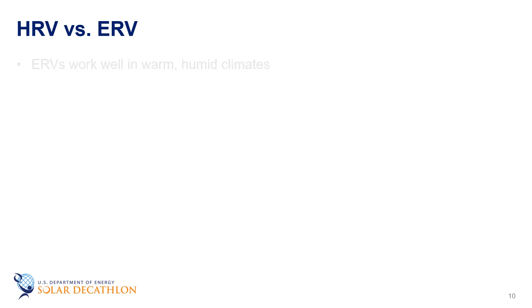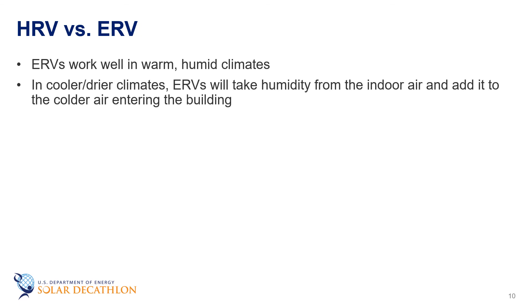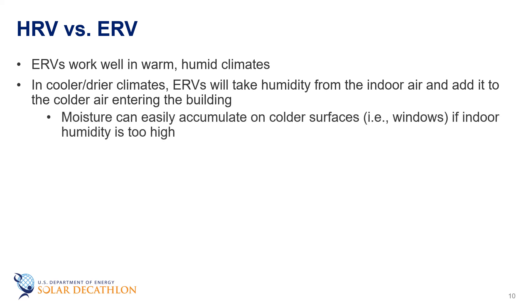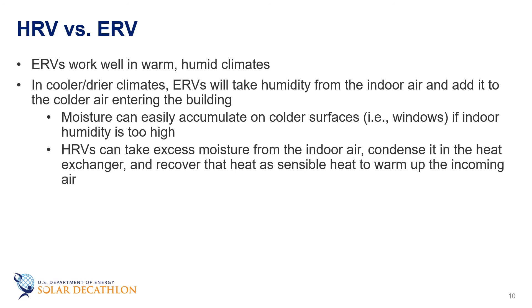As a caution, however, this works well in humid climates. As the climate becomes cooler and the heating loads dominate, the energy recovery ventilator will take the humidity from the air and add it to the cold air entering the space. You must be careful here as humidity can build up in the space, as humidity is generated from cooking, bathing, and perspiration. Too much humidity in the space will start to condense on cooler surfaces such as windows — this is an indication that there is too much humidity. A heat recovery ventilator can take this excess moisture, condense it in the heat exchanger, and recover that heat as sensible heat to warm up the incoming air.